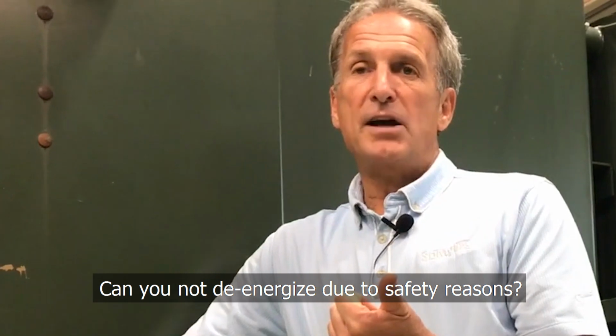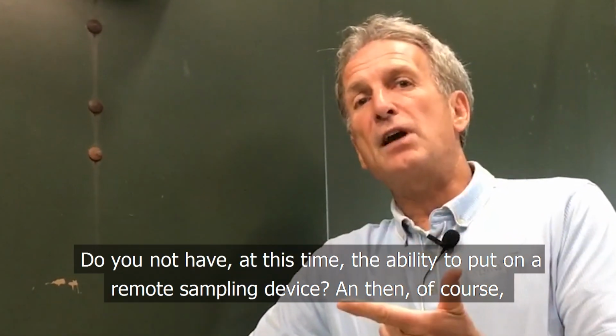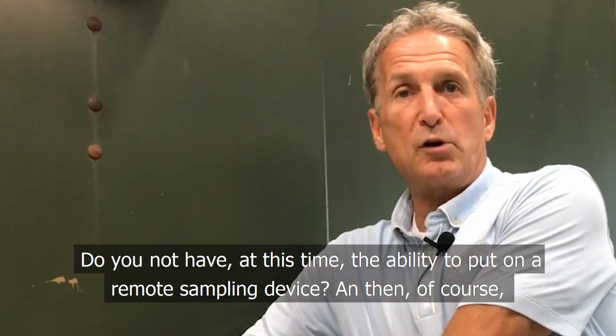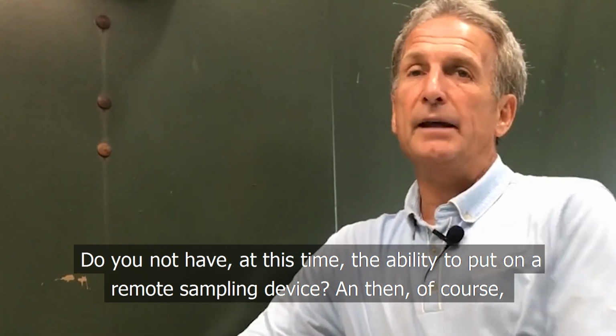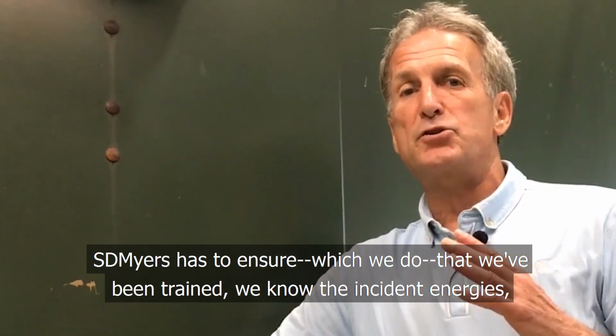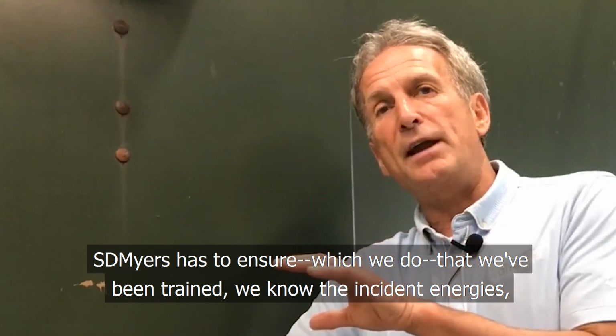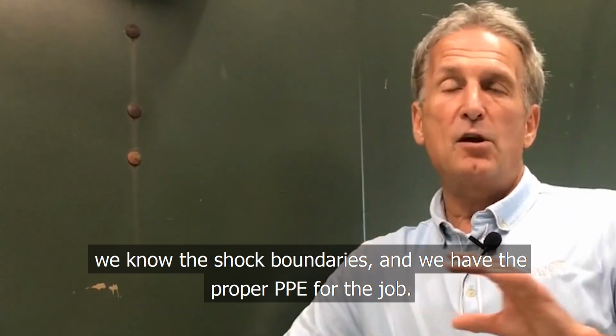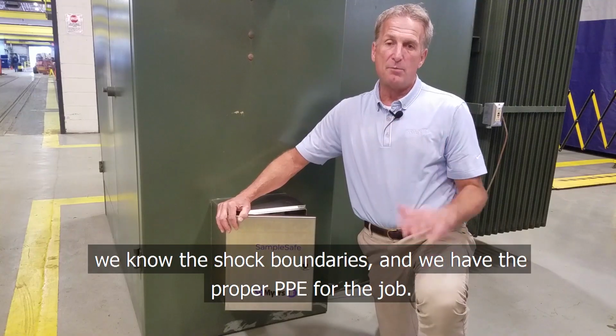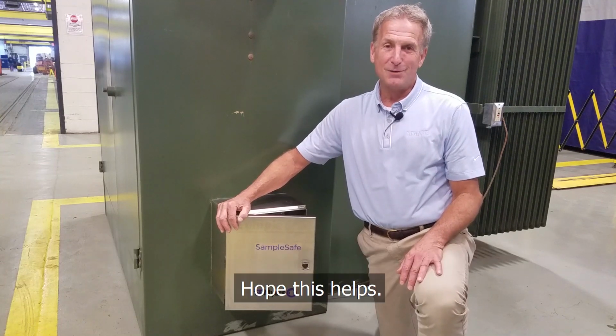Can you not de-energize due to safety reasons? Do you not have at this time the ability to put on a remote sampling device? And then of course, SD Myers has to assure, which we do, that we've been trained, we know the incident energies, we know the shock boundaries, and we have the proper PPE for the job. Hope this helps.